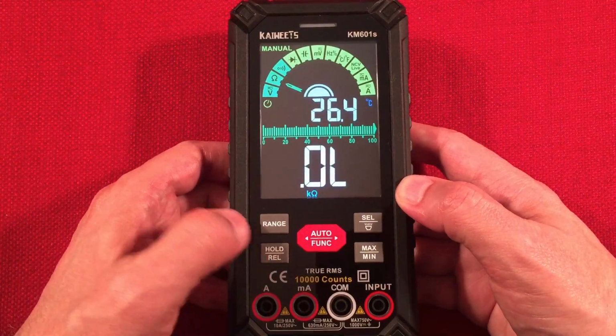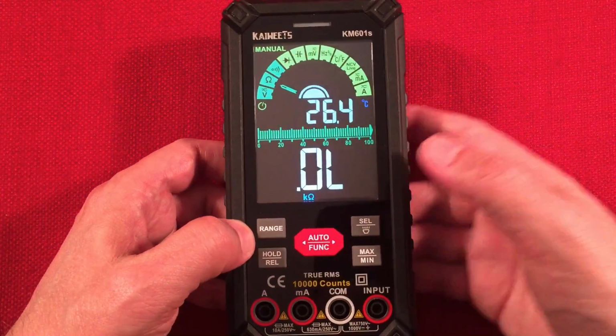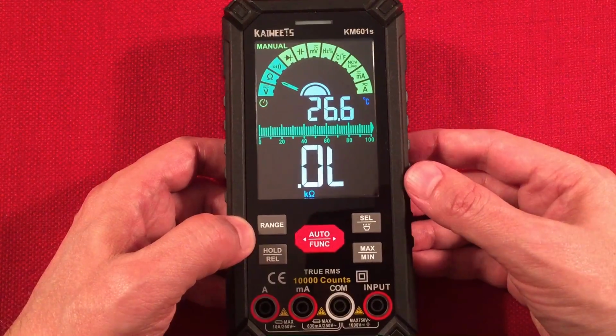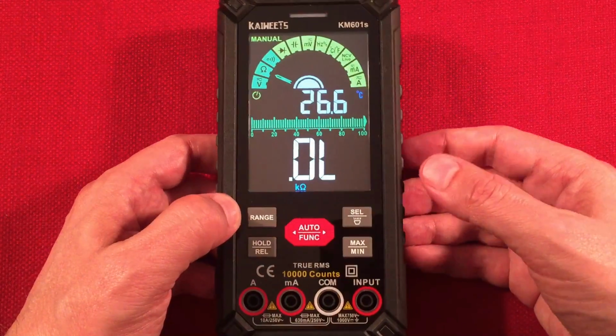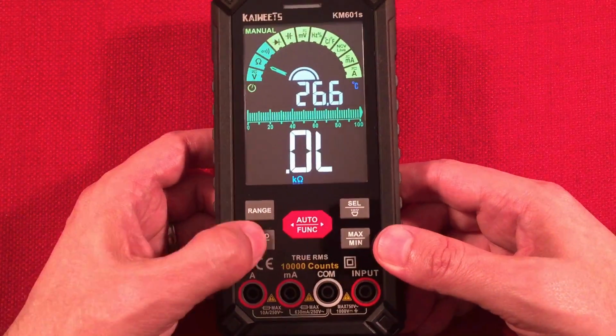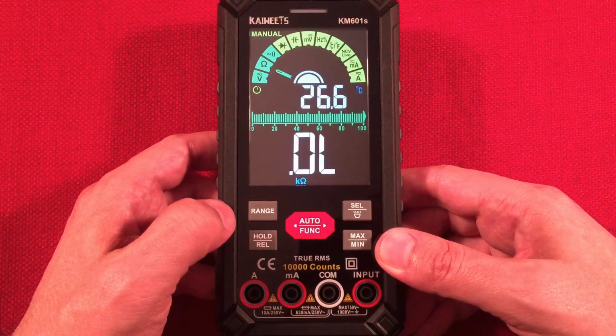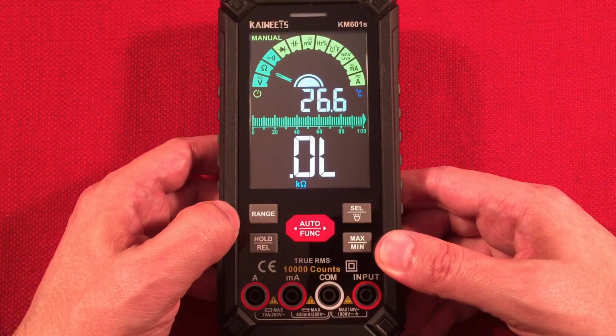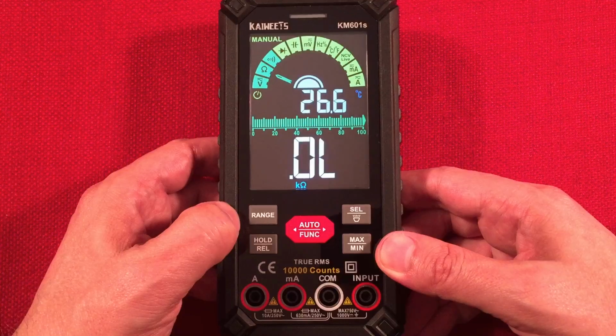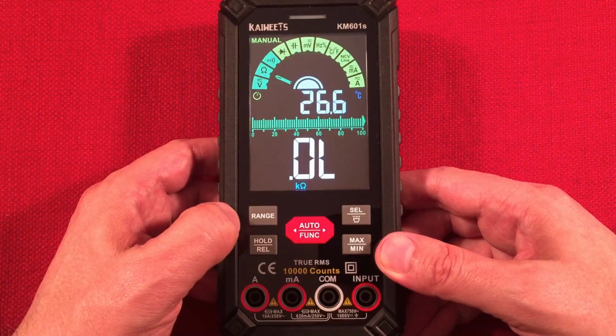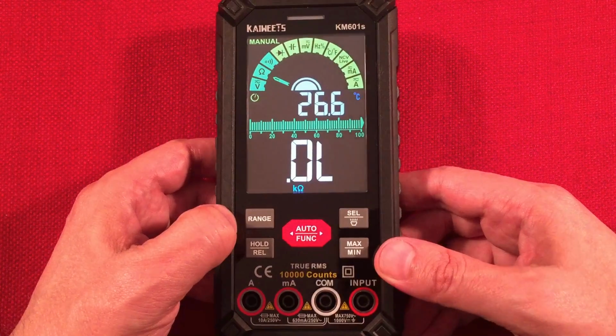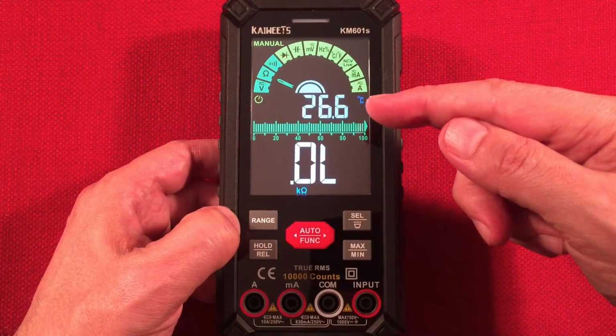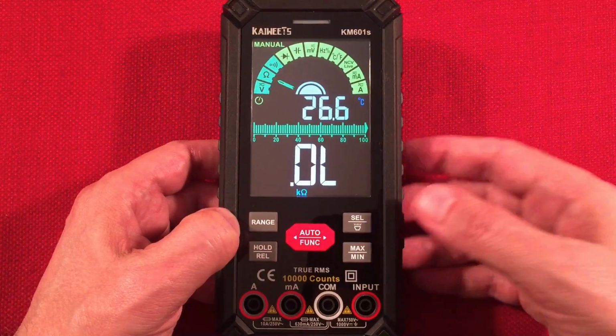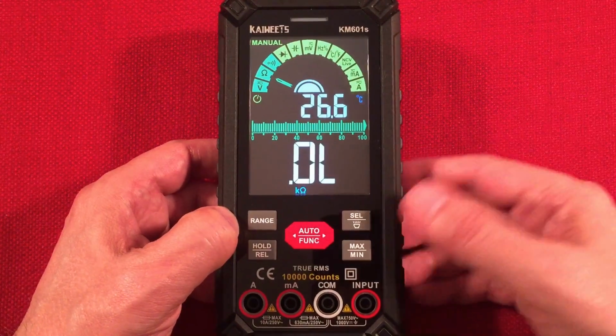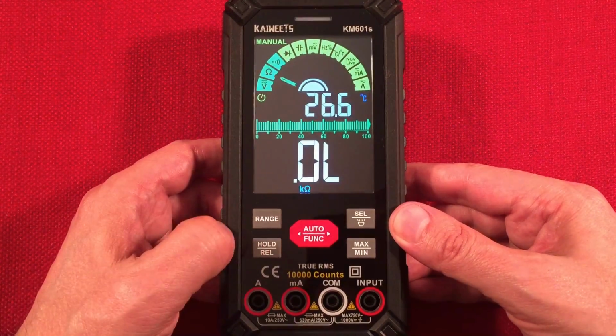What it does is zero out the reading. So say you're taking a measurement at 120 volts at the circuit breaker, and you press and hold this function — it zeroes it out. Then if you go to the outlet and measure there, it shows the difference. So it remembers that 120 value and just shows the difference now, which is nice. If it measures negative 1.2, you have a drop of 1.2 volts from the breaker to that outlet — that gives you an idea. That's a really neat button.